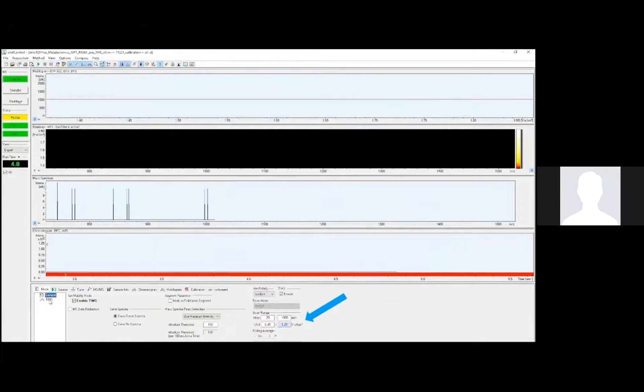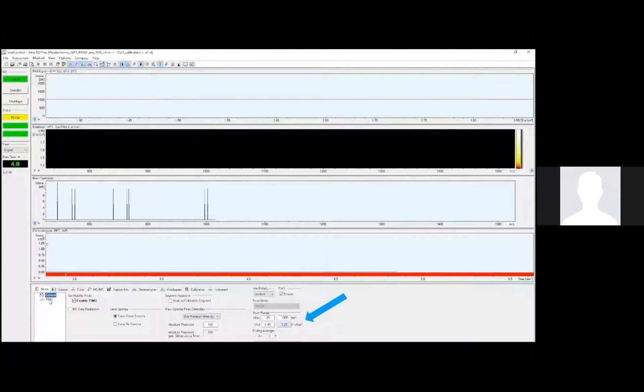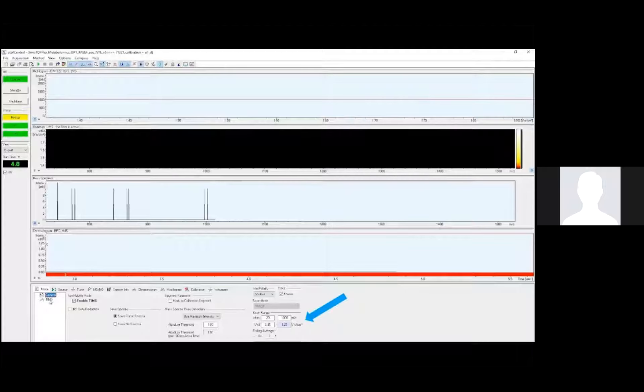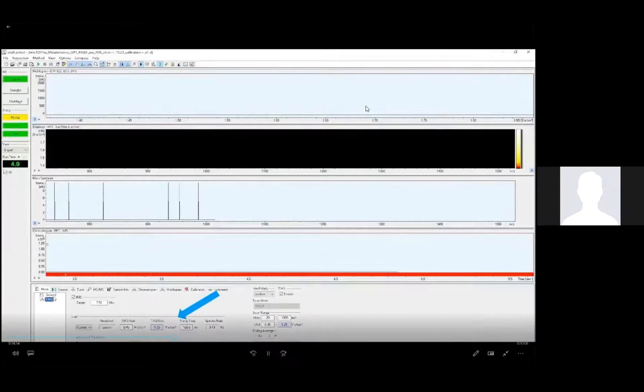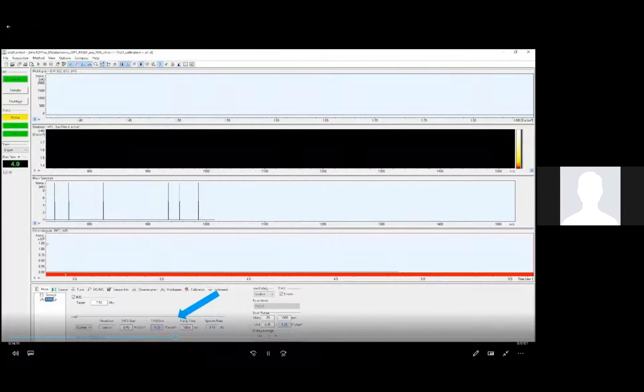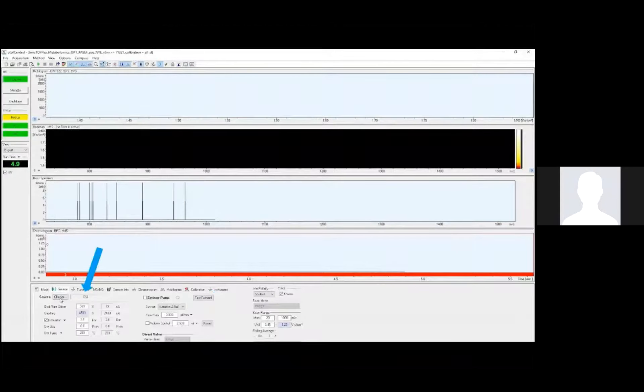Here's the positive TIMS-ON PASEF-enabled small molecules method that Bruker provided us, with some adaptations that I've made. I'll explain what a few of those terms mean as I go. Now I'll just walk you through some of the tabs in the OTOF control software. Here in this mode tab, the general settings let us turn TIMS-ON, set calibration segments, as well as a few other things. I'd also like to point out the scan range. The M over Z range is kind of self-explanatory. If anything falls outside of this range, the method will exclude it. The 1 over K-naught range is very similar but based on mobility. Anything outside of this mobility range will also be excluded by the software.